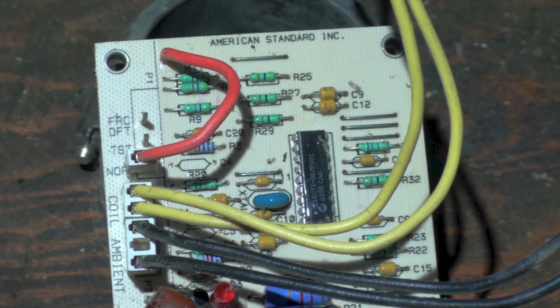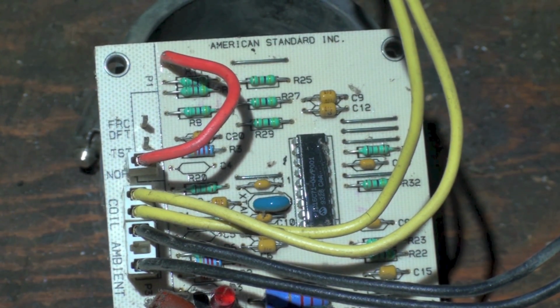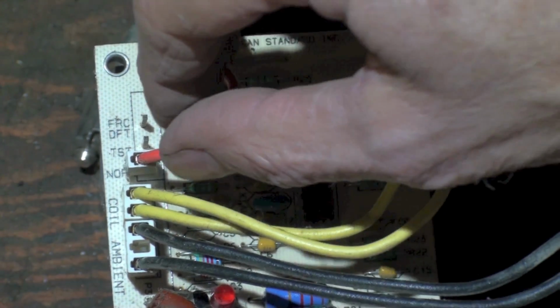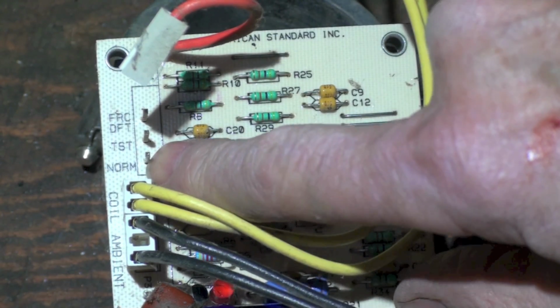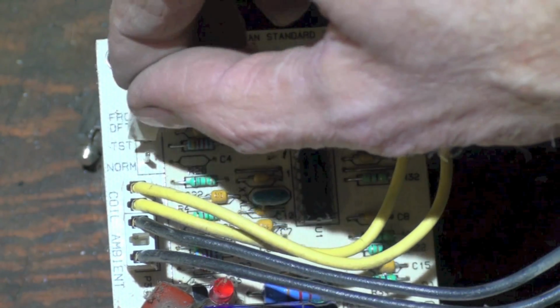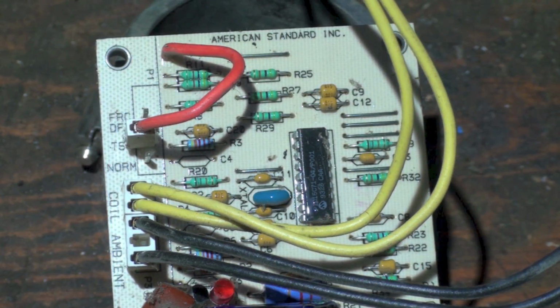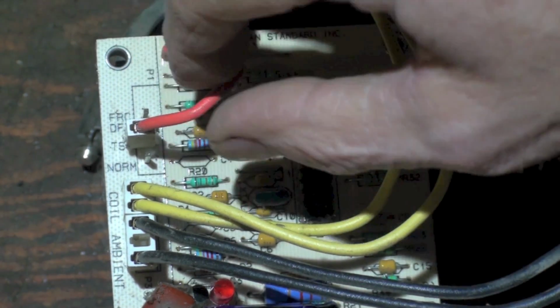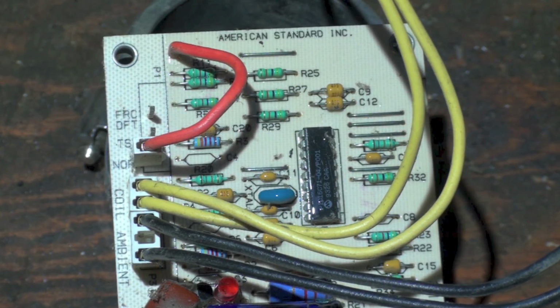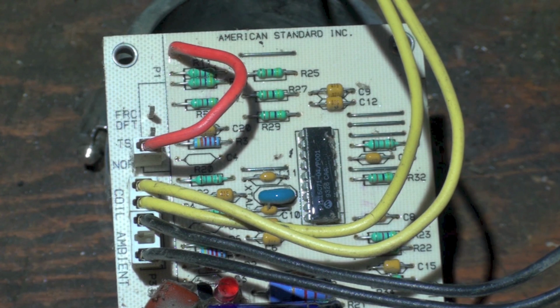Okay, looking close, I wanted to note here, there's a test for this thing. If you want to test to see if the operation is normal, you would take this wire, and you can see it says norm right there, put it in test, and it will go into defrost. When you're done, put it back in norm. If you leave it in test, it'll keep going in defrost. But that's a way to test that thing. You can test to see the reversing valve moves and be sure the fan shuts off and so on.